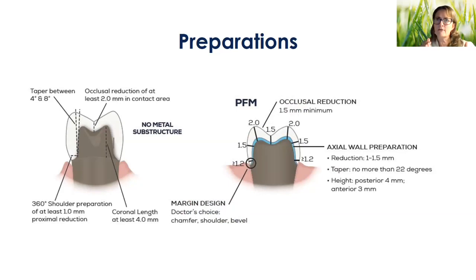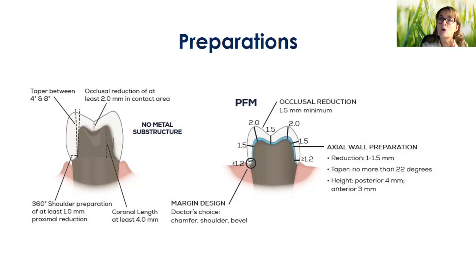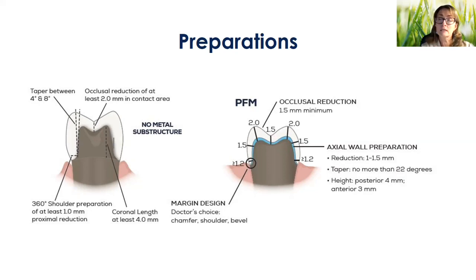The handout will also address preparation style. The most important thing to remember with the preparation is that all angles must be smooth and rounded — you don't want any sharp, squared-off line angles. When milling is occurring, it does not see into the sharp corners of those line angles. A chamfer or shoulder preparation is most desirable. When I go into a practice and ask the doctor what their go-to preparation looks like, if they say they like a little feather margin — a little knife edge, just tucked subgingivally — I never want to hear that. No scanner can really see that.